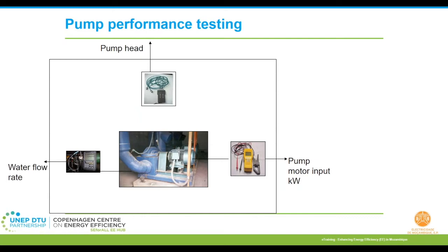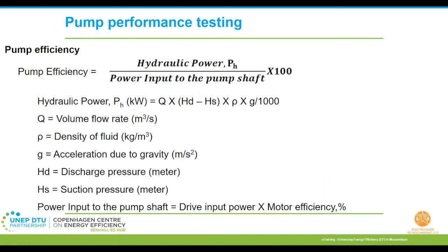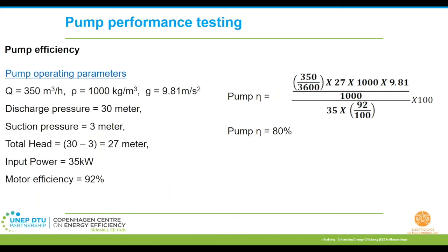For the pumps, generally you will be needing three important parameters that have to be measured, or you will be having these displayed in your BMS systems, the monitoring and control systems, if you have one. So it's basically the water flow, the pump head that is developed, and the power consumption. And this slide gives you how to evaluate the pump efficiencies. You can always evaluate the pump efficiencies and then compare them with the design details, and then you can see if there is any deviation, why it is deviating, and further investigation can be done. I'm giving you an example with numbers, how to evaluate pump efficiencies.